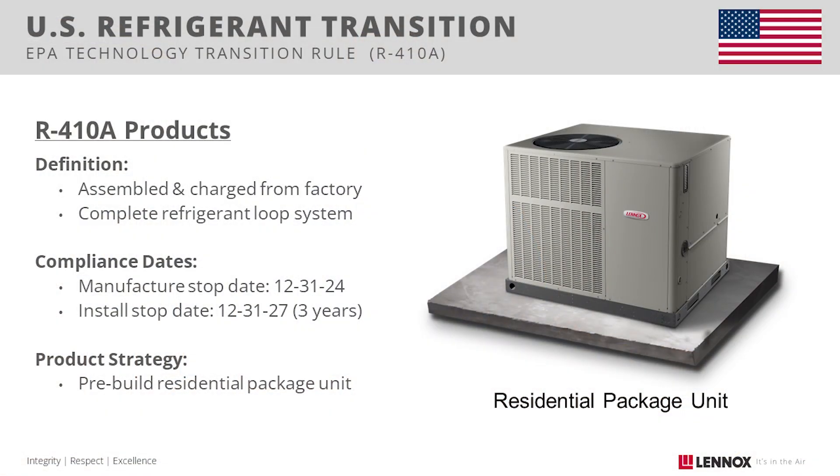First, we'll start with R410A products. The EPA definition of products refers to those that are assembled and charged at the factory as a complete refrigerant loop system. A prime example of a product is a residential package unit. There haven't been any changes to this rule. We will stop manufacturing by the end of 2024, and you will have a three-year install period or until inventory depletes.